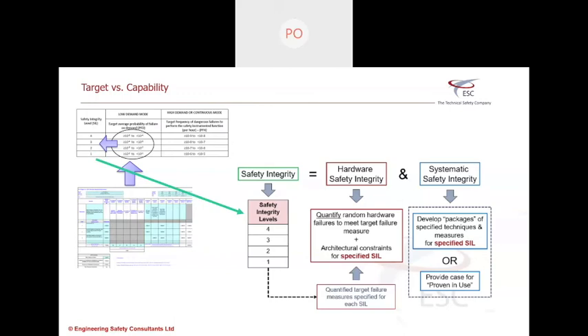Like the frequency of testing, the coverage of that testing, the recording of faults, the understanding and levels of investigation into failures when you needed the system to operate. And the reintegration into the analysis, refreshing that knowledge that you had when you first started and very likely only estimated what you were going to need. So, this is within the 61508 and 11 standards as an intrinsic part of how to do functional safety. And it isn't an activity with a start and a finish, but an activity with many, many loops of iteration depending on the operational phase or developmental phase of the product, asset or site.